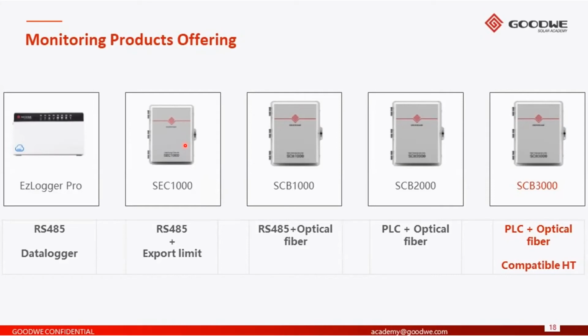So inside we have basically an EzLogger Pro, and we have a GoodWe smart meter inside, which is measuring the import and the export of the grid. And this information is then sent to the EzLogger Pro, which then controls the inverter and basically tells the inverter to either increase or decrease its active power output to maintain the export limit at the point of connection.